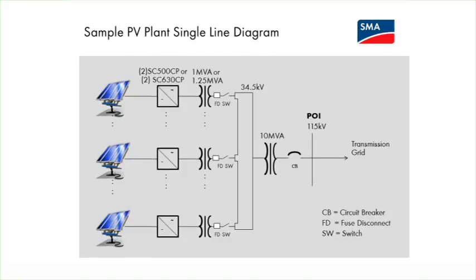Now, what do we mean by point of interconnection? This is an example where the point of interconnection is at the 115 kV bus, and what we're showing here is a PV power plant that has medium voltage step-up transformers to 34.5 kV, and then steps it up to what we call 115 kV, or transmission level.